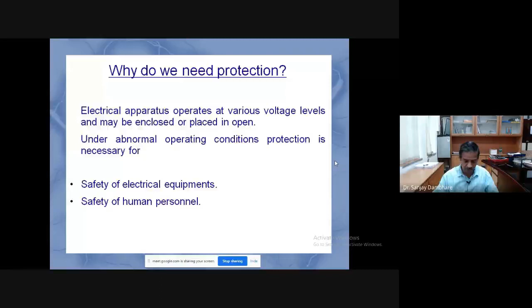So these protective devices, like relays, get the information of the power system through the CTs and PTs. CTs and PTs are treated like the ears and eyes of the power system, and you get the information of the power system in the protective relay through these CTs and PTs. The primary of the CTs and PTs are connected to the high voltage side of the power system, and at the secondary you get very low voltages and currents, which are the faithful replica of the primary current.